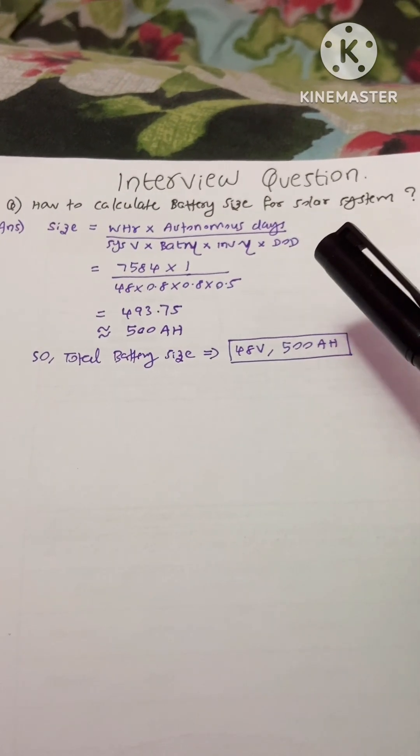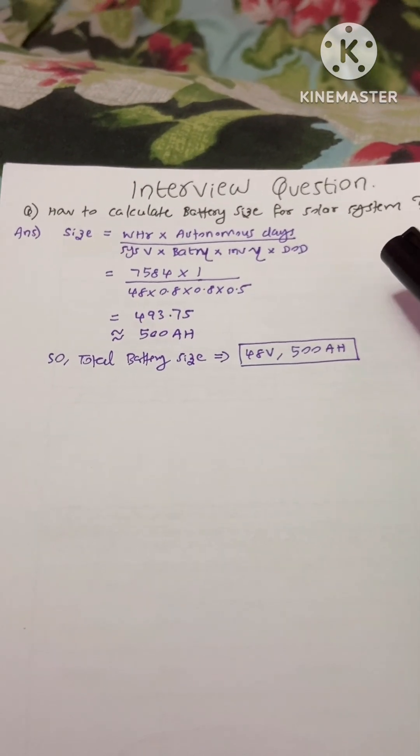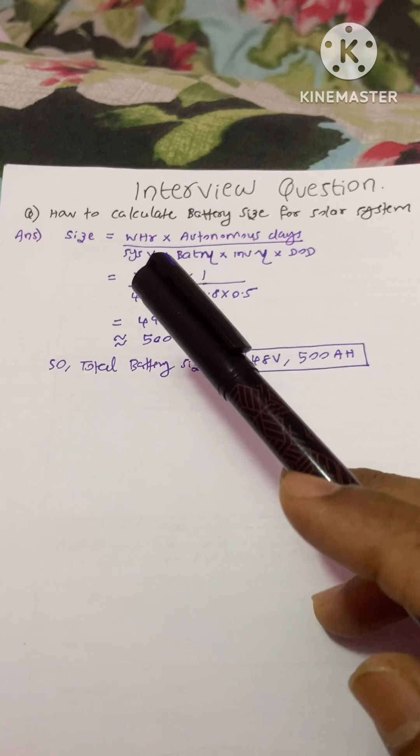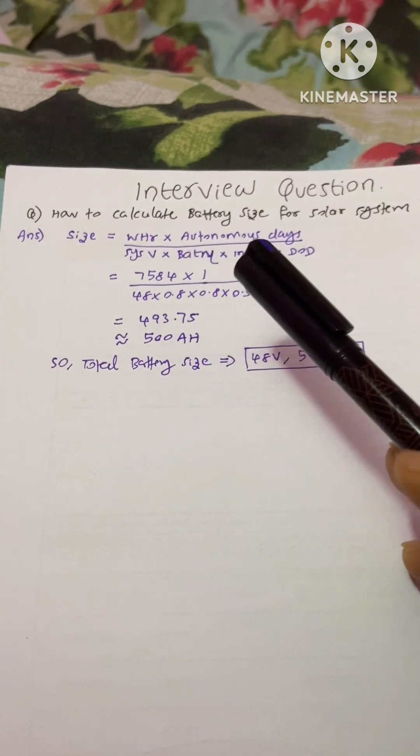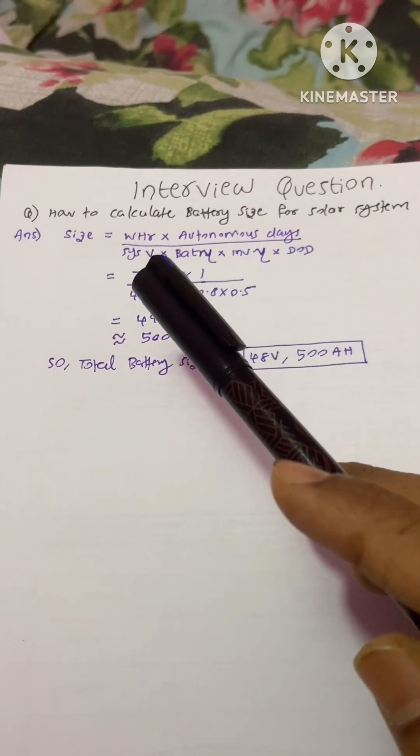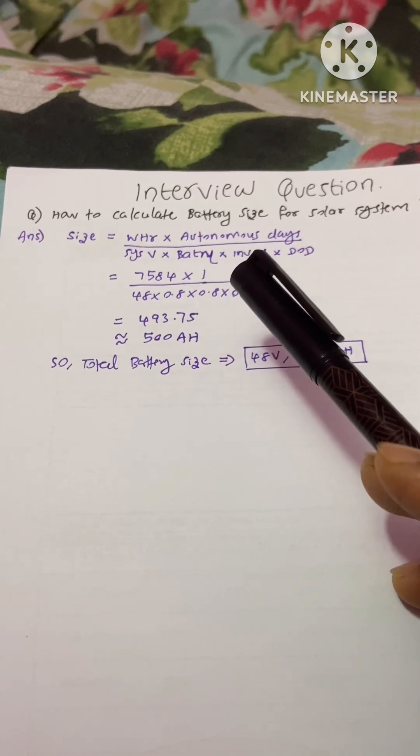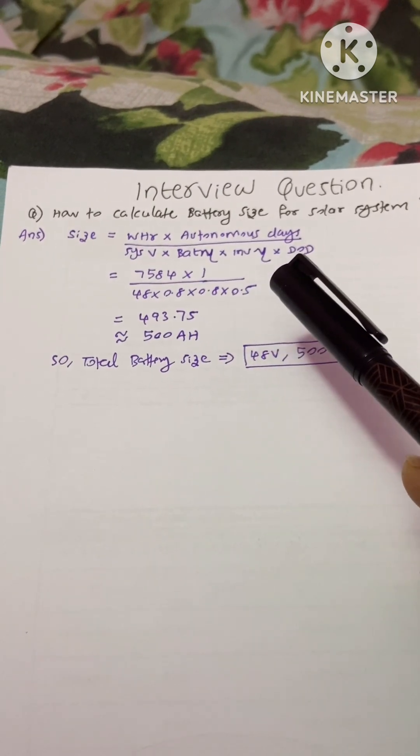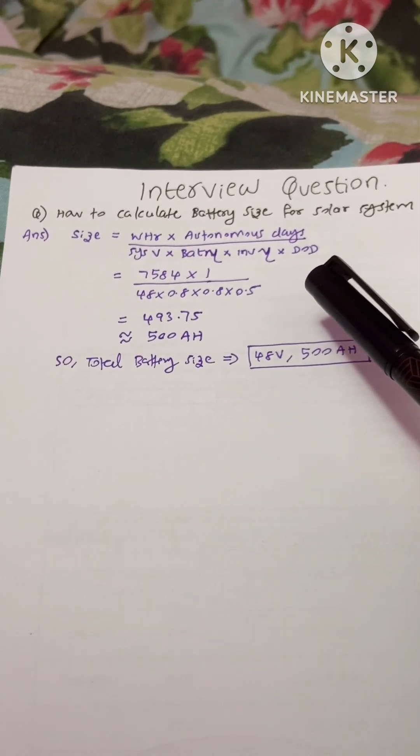How to calculate battery size for your solar system? The equation is watt hour times autonomous days, divided by system voltage times battery efficiency times inverter efficiency times DOD depth of discharge.